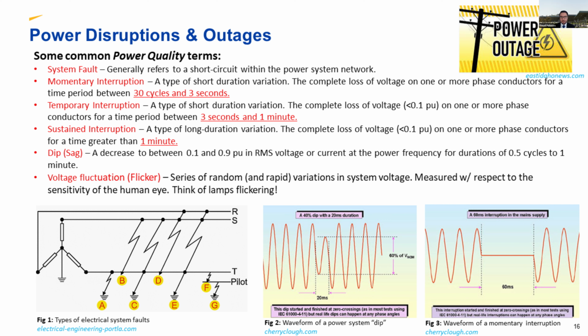All of these things can be caused by certain disruptions of the power system, whether at the city level, substation level, or within our internal power distribution level. The last figure, figure 3, is just a representation of a momentary interruption, which again is anywhere from 30 cycles to 3 seconds. This example is showing a little bit more than that, 60 milliseconds of a momentary interruption. This could wreak havoc on very sensitive electronic equipment within research buildings and rooms.